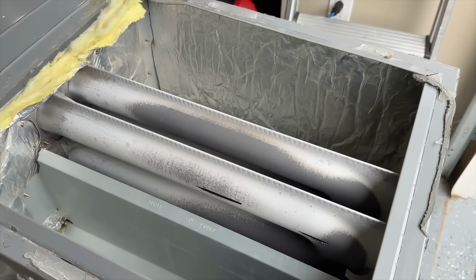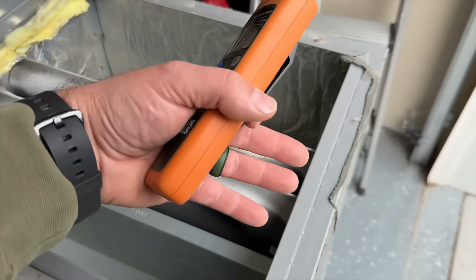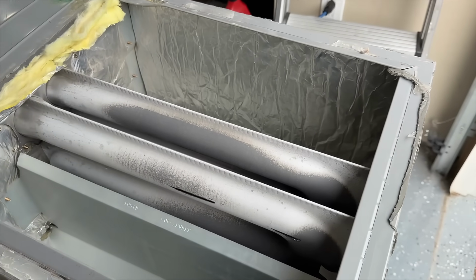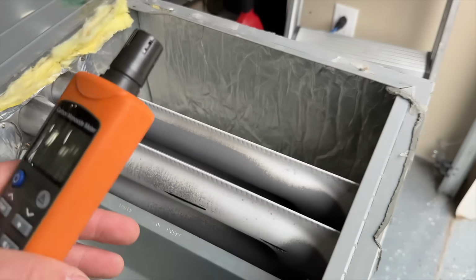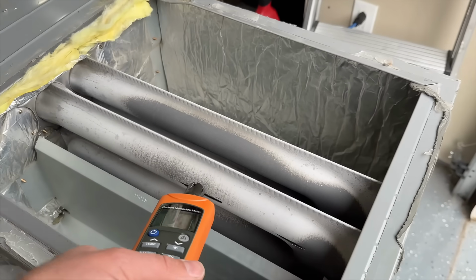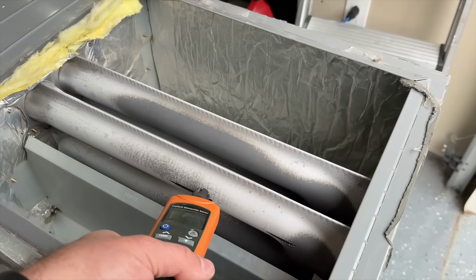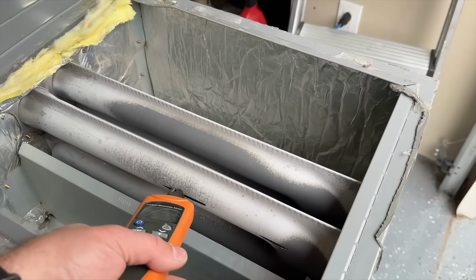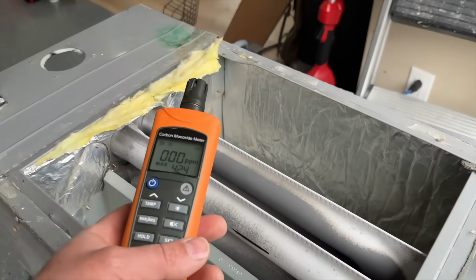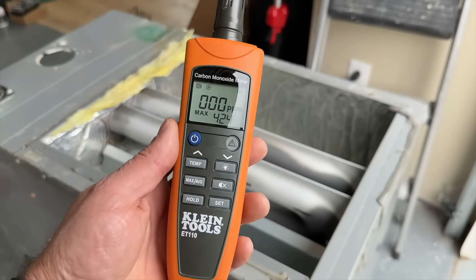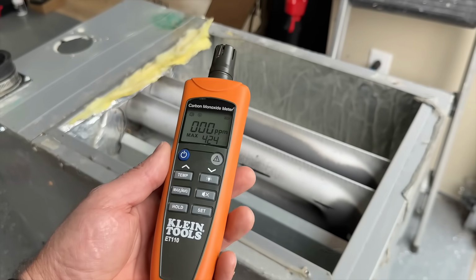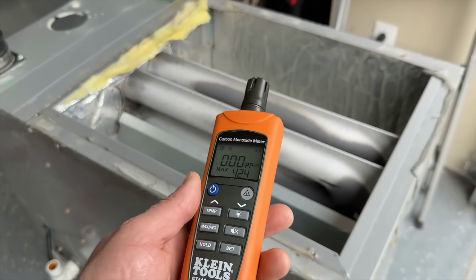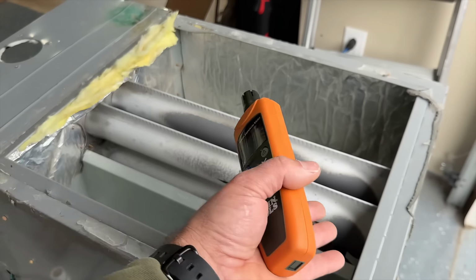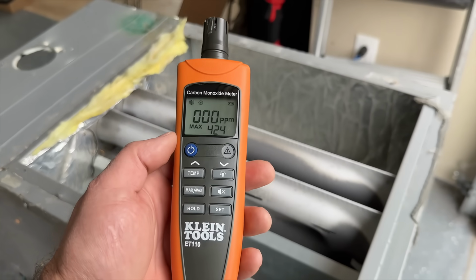So this emphasizes that the heat exchanger is under a vacuum. The inducer is pulling that flame through, and it's not allowing any carbon monoxide to escape. You have to have a massive, massive crack in order for that to happen. So I thought I'd just show you this. This is not something that you'd typically see, but I wanted to show you how this actually works and what you can expect on an active crack on a heat exchanger.